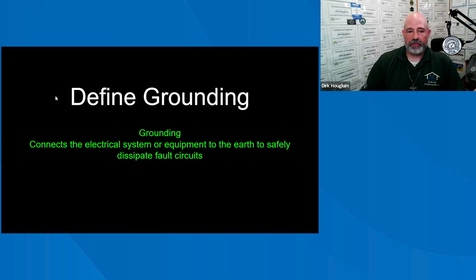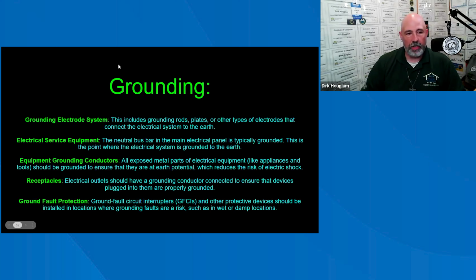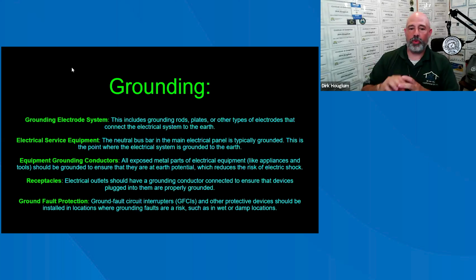Define grounding. Grounding connects the electrical system and equipment to the earth to safely dissipate fault currents. Grounding electrode system: this includes grounding rods, plates, or other types of electrodes that connect the electrical system to the earth. Electrical service equipment: the neutral bus bar in the main panel is typically grounded together. This is the point where the electrical system is grounded to the earth. So your neutrals and grounds have to be connected at the main panel only. After that, it has to be bonded throughout.